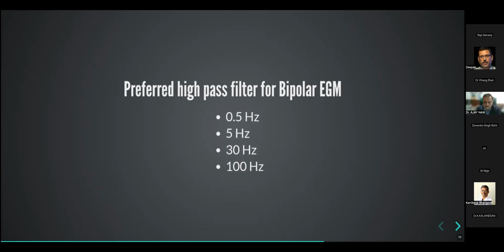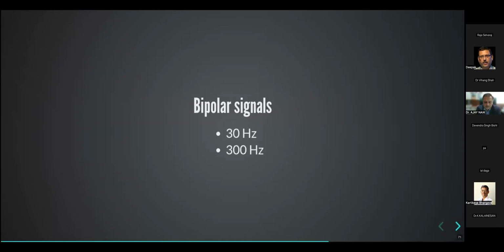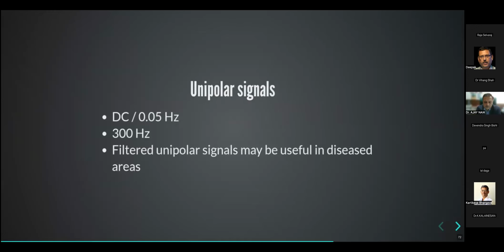Okay, so most of you have got the answer right, 30 hertz. Because in a bipolar EGM, like we said, we are not very interested in low frequency signals, and therefore a 30 hertz cutoff is enough. For bipolar signals, usually we do 30 hertz, and the upper cutoff can go to 250, 300, or 500 hertz. For unipolar signals, like I said before, the lower cutoff can be DC filtered, which means basically 0 hertz, or a very low value like 0.05 hertz. The upper can go to 300 hertz, and you can use filtered unipolar signals where, instead of using DC or 0.05, you use a 30 hertz filter, then it's called a filtered unipolar.